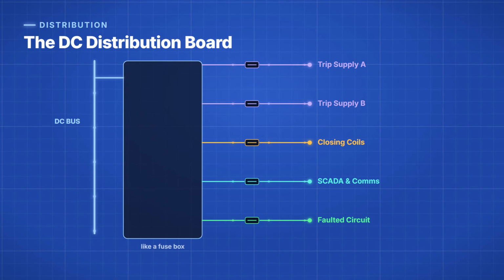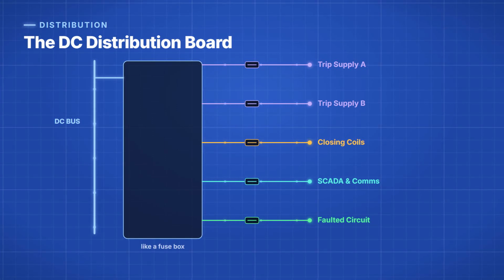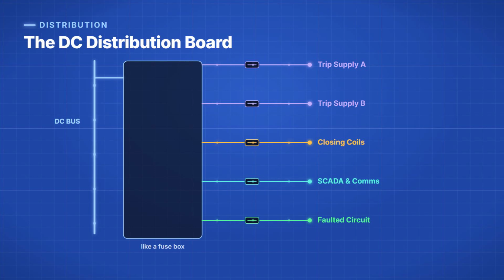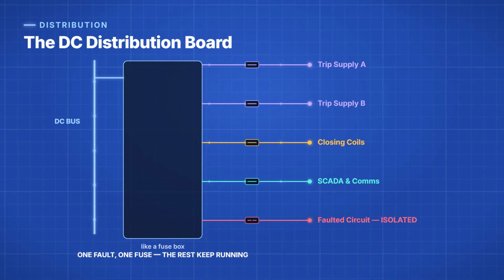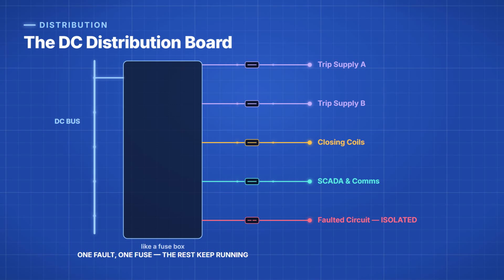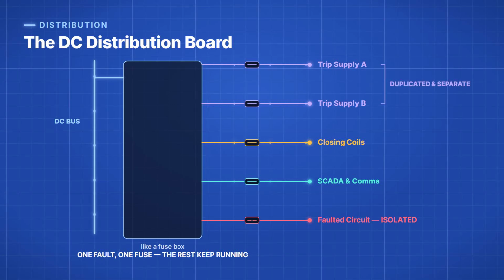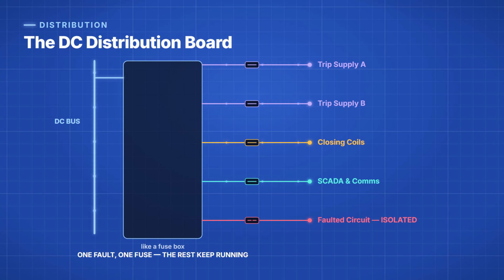Think of it as the fuse box for the whole DC system. Each outgoing circuit, which we call a feeder, leaves through its own fuse or miniature circuit breaker. That way, a fault on one circuit blows only its own protection and the rest of the DC system keeps running. Critical circuits, like the trip supplies, are often duplicated and kept separate so that a single problem can never take the protection offline.